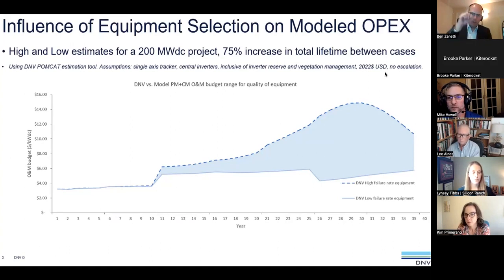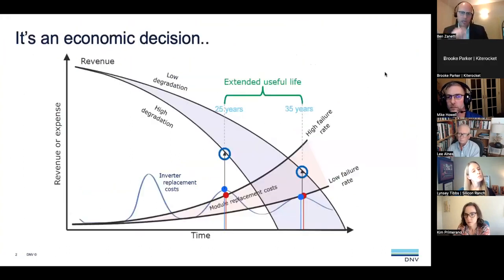If I go to the previous slide, I'll show you. You'll see there's the first inverter replacement curve, around 10 years, typically 10 to 15. Then there's a follow-up again 10 years after that, a second round, and if you're up to 35 or 40 years, there may be a third round. A lot of people don't necessarily plan for that in the early stages, so it's very important to ensure that's integrated into your plans.